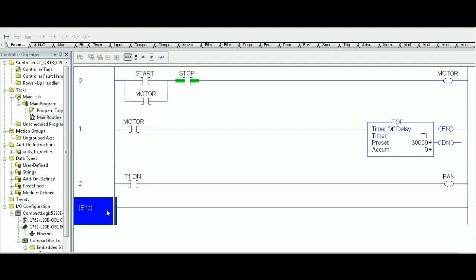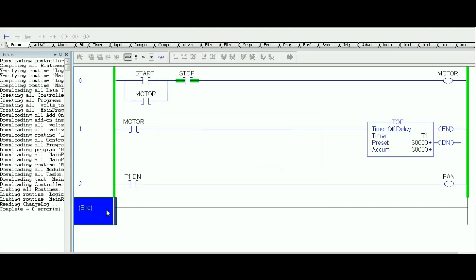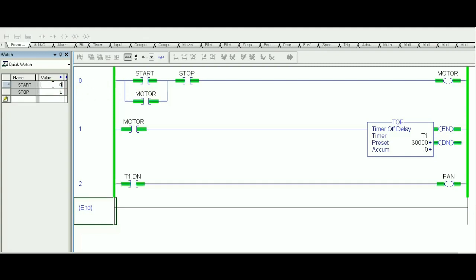Let's download this and see how it works. Right now with TOF, the accumulator starts equal to the preset value, which makes the Done bit equal to zero, so the fan is off and the motor is off because Start has not yet been pressed. Pressing Start does two things: it energizes the motor via the start-stop latch, and it resets the TOF timer — the accumulator goes to zero and the Done bit becomes true. So both motor and fan are now on.